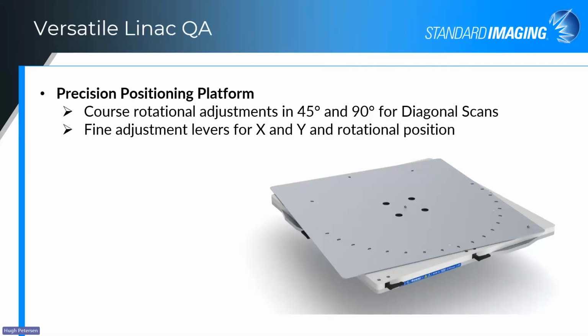A little more on that positioning platform. You have the coarse rotational adjustments that lock in at either the 90 degrees or those 45s if you want to do diagonals. And then you can see on the edges there are black fine adjustment levers for X, Y and rotational. So you get it into your coarse position, and then you have up to 2 centimeters of movement with those levers to fine tune the position of the water phantom. And it sits on a self-lubricating Teflon platform, so it rotates even with water in it. You can move it and rotate it on that platform.